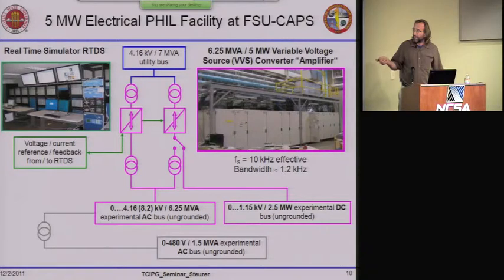And by having this relatively high switching frequency for a power rating of 5 megawatt, we are able to utilize a bandwidth up to 1.2 kilohertz. So we can reproduce unbalanced voltage waveforms. We can introduce harmonics and so forth, frequency deviations and the like.